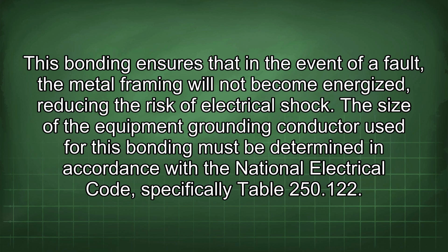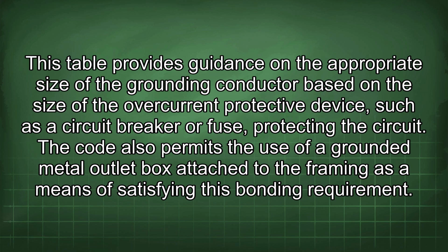The size of the equipment grounding conductor used for this bonding must be determined in accordance with the National Electrical Code, specifically Table 250.122. This table provides guidance on the appropriate size of the grounding conductor based on the size of the overcurrent protective device, such as a circuit breaker or fuse protecting the circuit.